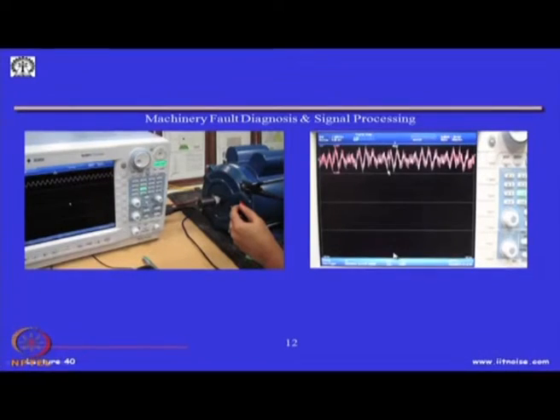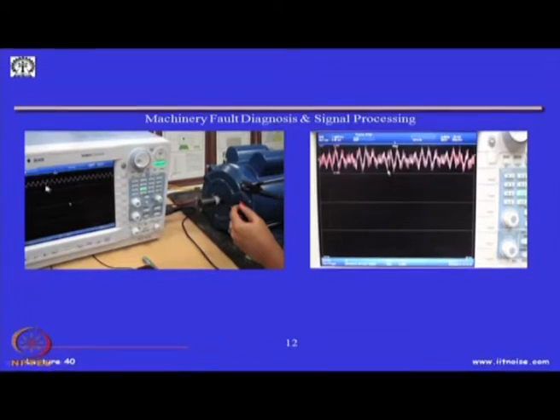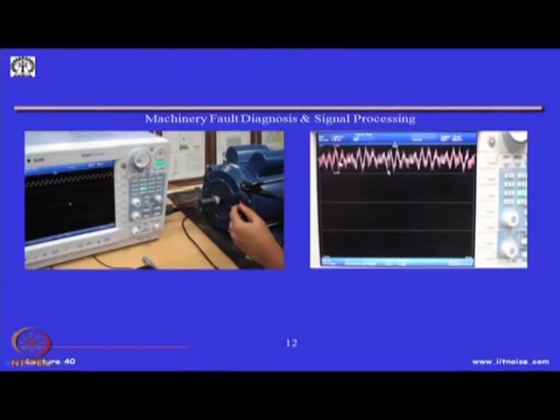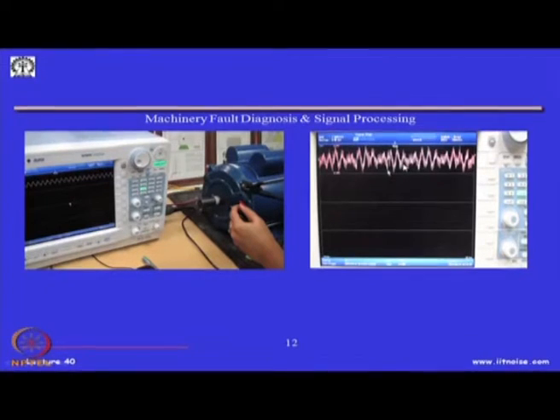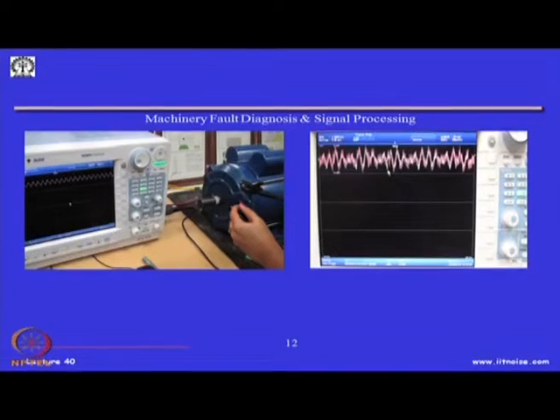This is an example I am showing in the laboratory: in one case a motor was not driven by a VFD drive but by the normal power supply. You can see a nice low amplitude voltage at 50 Hz — that is the running supply frequency. But whenever we change the power supply through a VFD you can see high levels of peaks occurring because of such VFD drives. This is what we are measuring between the shaft and the ground — these kinds of peaks do happen. This has to be avoided — these are high frequency peak signals and they are responsible for spark erosion of the bearing seats.